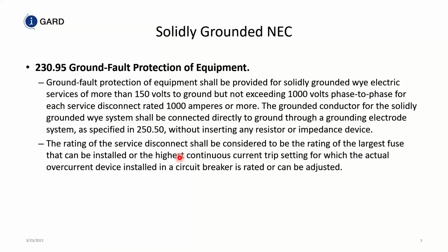So in the United States, National Electrical Code 230.95 says you must have ground fault protection on systems that are rated 150 volts to ground and greater than 1,000 amps. And you must put ground fault protection in all the disconnecting devices. You probably already know this with the LSIG function of your breakers. It's predominantly low voltage breakers, but this can apply to medium voltage breakers as well, well, not exceeding 1,000 volts.